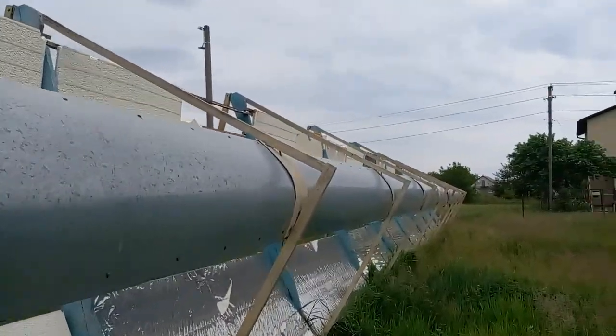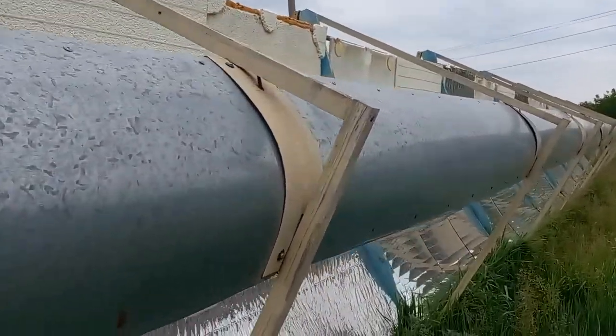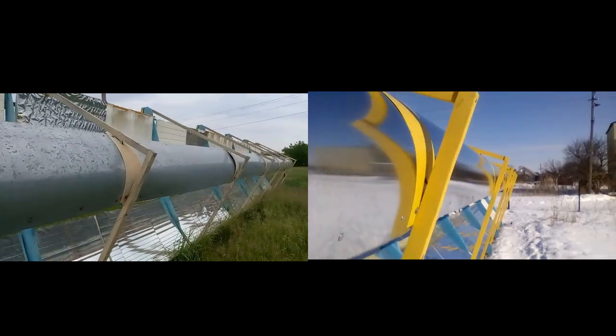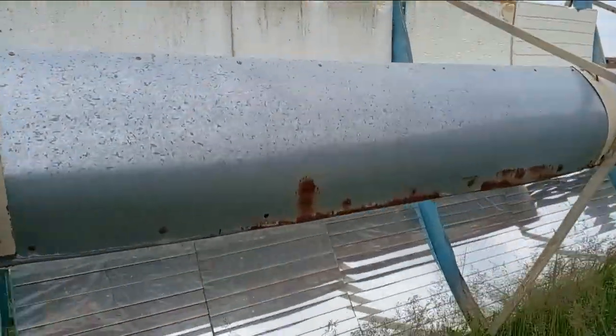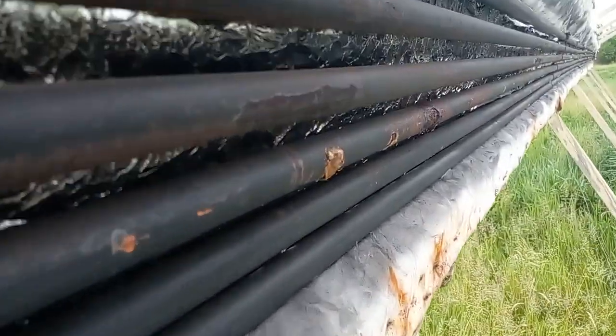These are those metal sheets after 6 years of use in the open air, and this is cheap galvanized steel with a thickness of 300 microns. Now on the right there is the same receiver but 6 years ago, and we understand that the lifespan of the receiver will be more than 10 or 20 years, but here we see corrosion. The technical condition of the pipes was shown in the previous video.